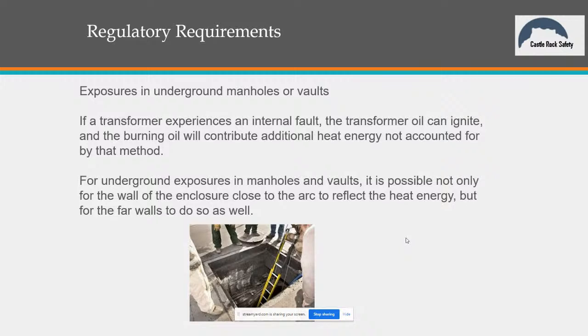And so I get asked all the time, well, if I do my calculation and I've only got 8 calories of exposure down there, should I put a 40-calorie suit on? Well, you could, but it's still only going to be 8 calories. It's 8 calories, 8 calories. You've got all these other things to deal with.